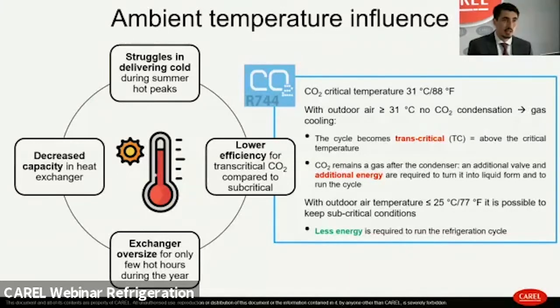Everything I've just said is especially true for CO2, since we are working in two different modes, transcritical and subcritical, according to the ambient temperature. Let me explain it better. Since the CO2 critical point is quite low, around 32 degrees Celsius, working above this temperature, which can happen with the ambient temperature we face especially during summer, we have to work in transcritical conditions. That means the CO2 no longer condenses in the heat exchanger; there is just a gas that cools down.